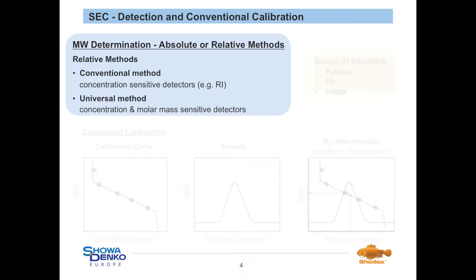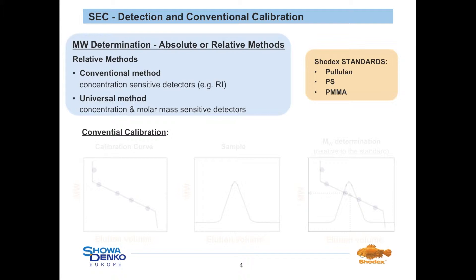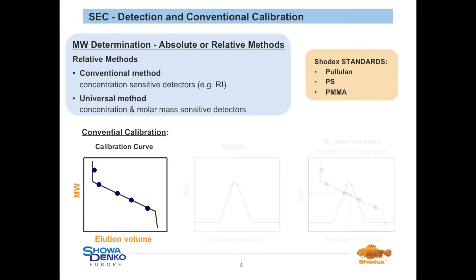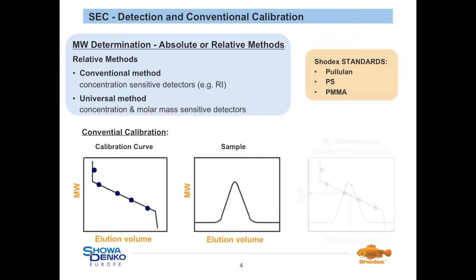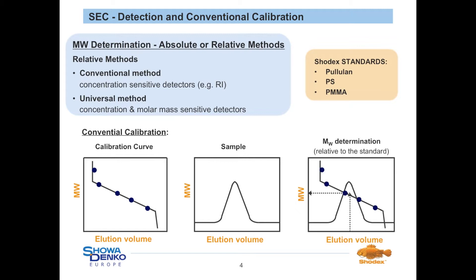The relative method can be divided into conventional and universal calibration methods. In the case of conventional calibration, only concentration sensitive detectors — in most cases RI detectors — are used. For universal calibration methods, concentration sensitive detectors are combined, preferably with viscometers which are molar mass sensitive detectors. For both calibration types, standards with known molecular weight and narrow molecular weight distribution have to be used. Shodex is also offering standards, i.e. pullulan for aqueous applications, and polystyrene and polymethylmethacrylate for applications in organic solvents. First, standards with known and different molecular weights are analysed and a calibration curve is created. In the second step the sample with the unknown molecular weight is analysed, and finally the molecular weight of the sample can be determined relative to the standard.